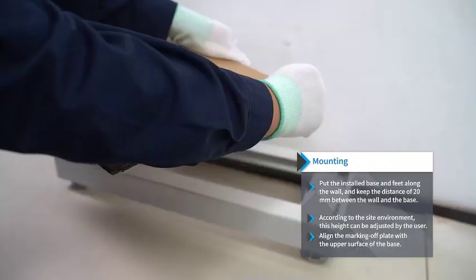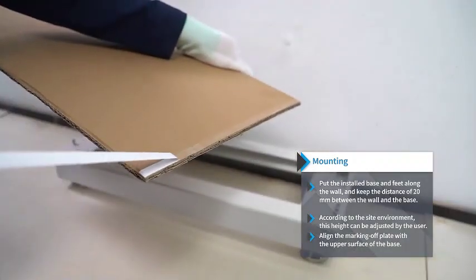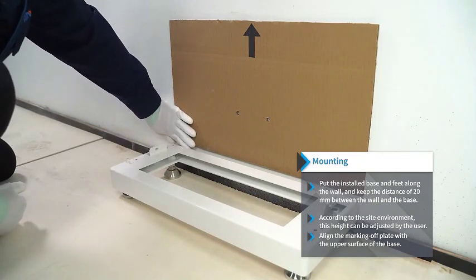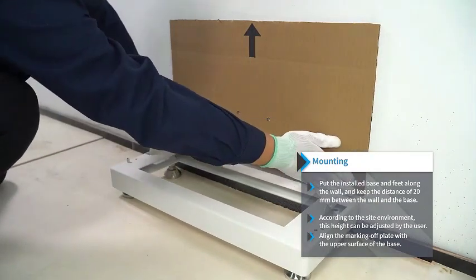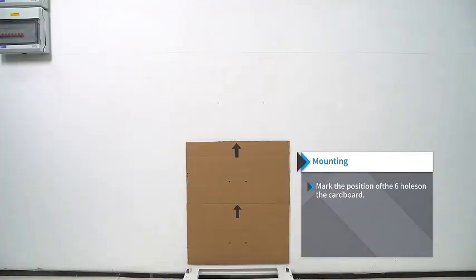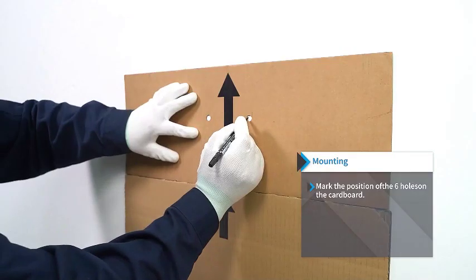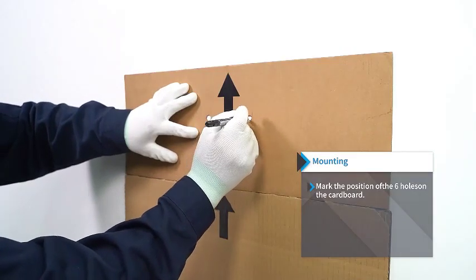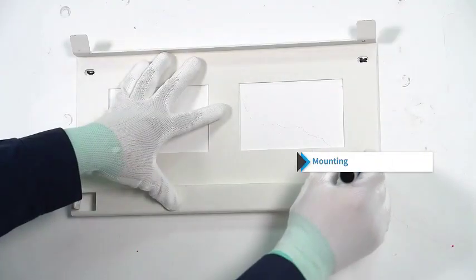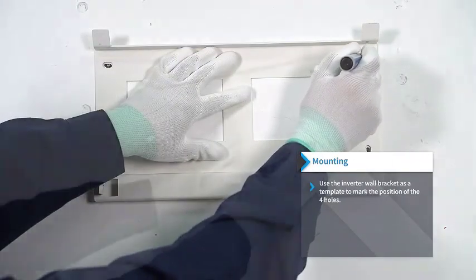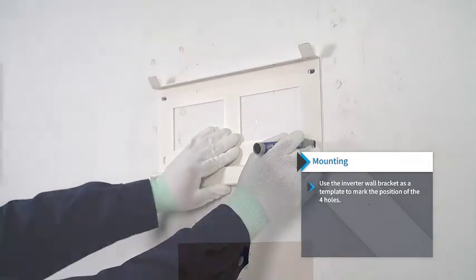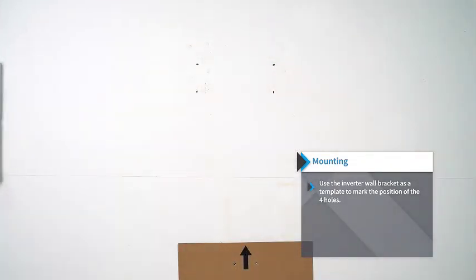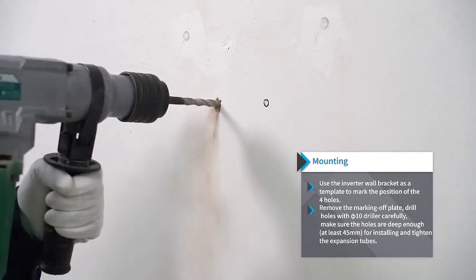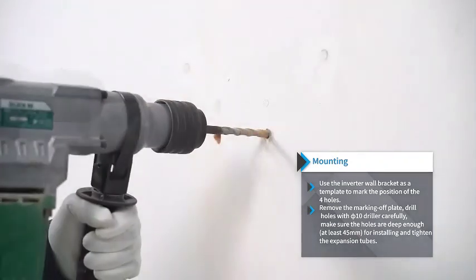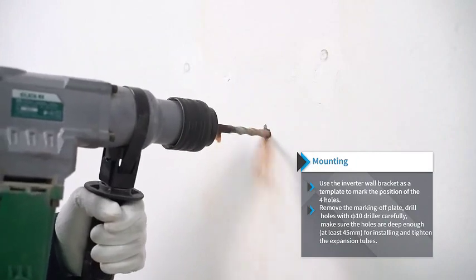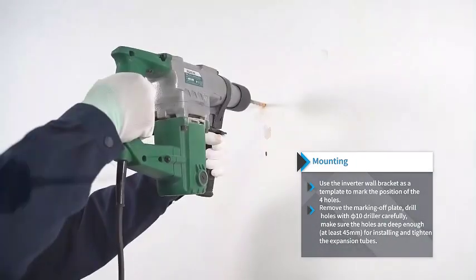Align the marking-off plate with the upper surface of the base. Mark the position of the 6 holes on the cardboard. Use the inverter wall bracket as a template to mark the position of the 4 holes. Remove the marking-off plate and drill holes carefully with a 10 driller. Make sure the holes are deep enough, at least 45 millimeters for installing, and tighten the expansion tubes.